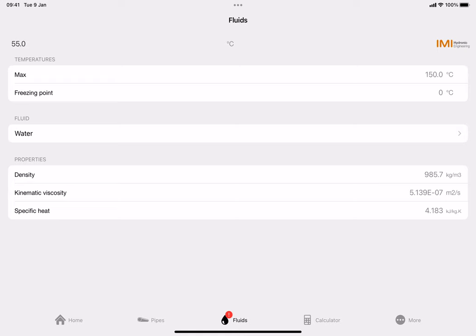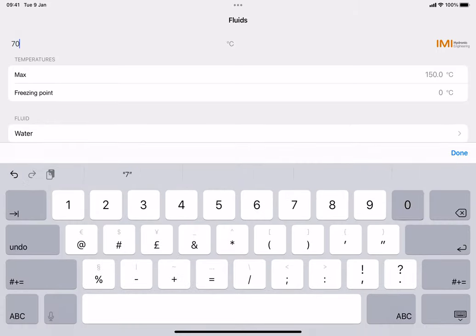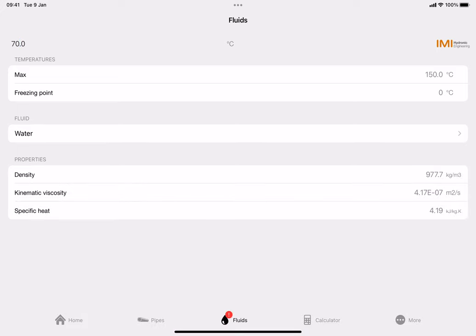If you click 'done' you'll see down at the bottom right-hand side the specific heat at 55 degrees of water on its own is 4.183 kilojoules per kilogram Kelvin. It doesn't change much, but if you're doing big commercial projects it can make a difference between going up or down a pipe size. If you're specifying 300 meters of say DN250 and you go to DN300 because of the calculation, the price difference between 250 and 300 could win or lose you a project. If we change to a more traditional 70 degree flow temperature you get 4.19 - this will make absolutely no difference on domestic calculations very rarely unless there are hugely long runs of pipe work.